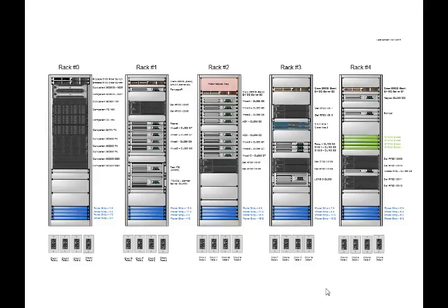What we do is we make sure that when we're dealing with a server, we'll take one power supply and it gets tagged to a circuit on panel A. The other power supply gets plugged into a circuit on panel C. So again, we could lose an entire panel or an entire UPS, and that's the other piece of this, we have multiple UPSs back there as well. So panel C is into 1 Liebert UPS, panel A is into a second Liebert UPS. I could lose an entire Liebert system and still be providing power to all of this gear through the other Liebert system.